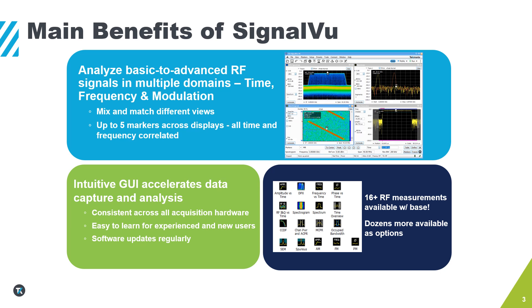Second, built upon 20 years of R&D innovation, SignalVu features an intuitive user interface that accelerates the process of data capture and analysis. It offers a consistent look and feel across all supported acquisition hardware and is easy to learn for both experienced and new users with regular software updates. And third, unlike other vector signal analysis software that may nickel and dime you for each feature, SignalVu offers 16 or more RF measurements standard with the base version. Some of the standard measurement displays include spectrum displays, spectrograms, RF I&Q versus time displays, channel power, occupied bandwidth, spectral emission mask test, spurious analysis displays, CCDF, MCPR, as well as amplitude, frequency, and phase modulation analysis displays. In addition, the base version of SignalVu is free to download and use on either a Windows PC or instrument for offline analysis of waveforms captured by all Tektronix spectrum analyzers and oscilloscopes.